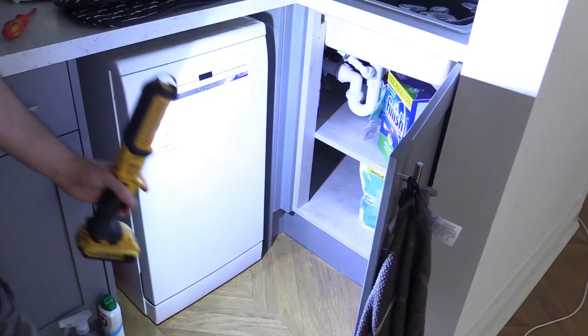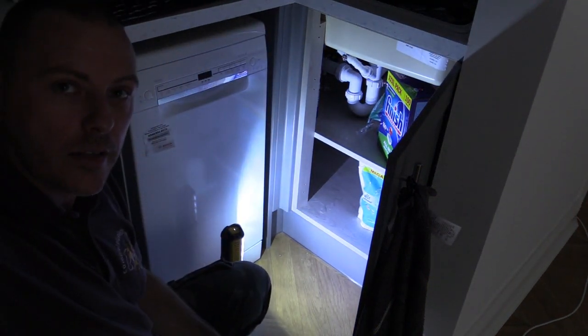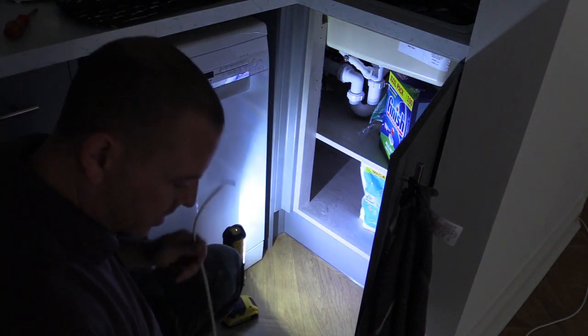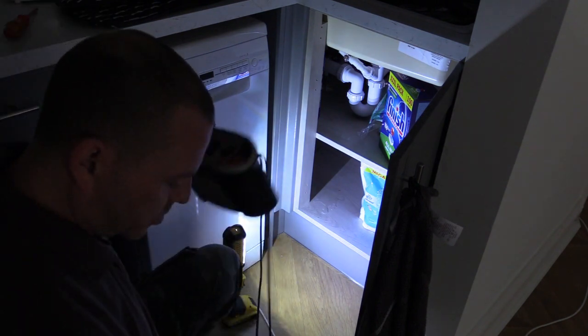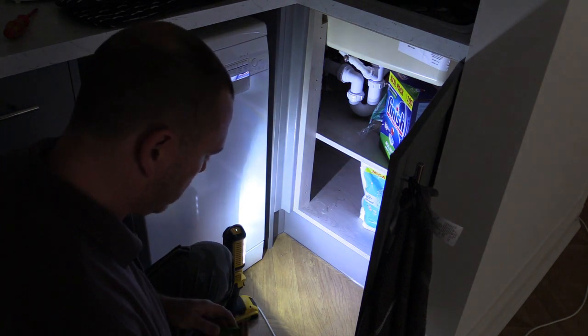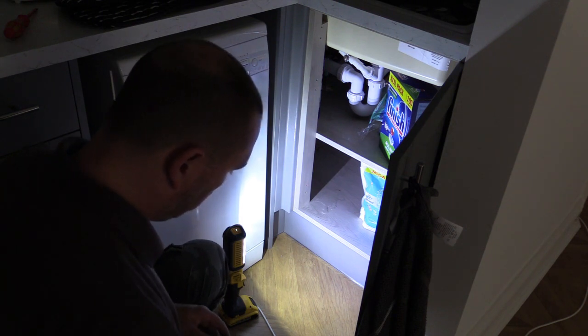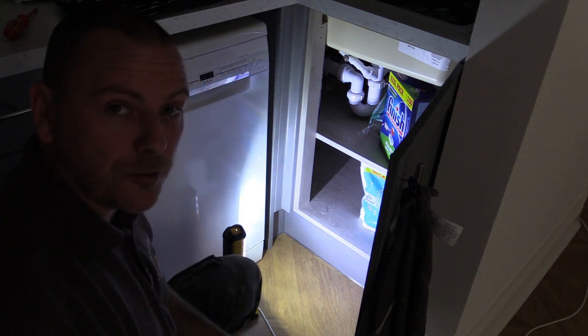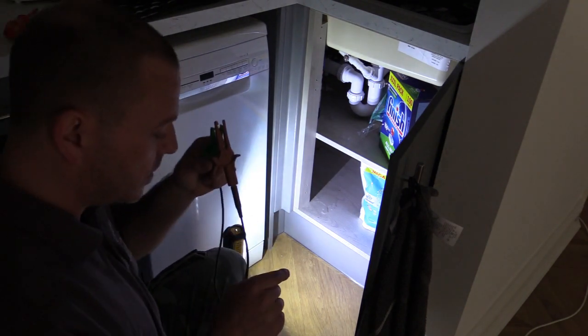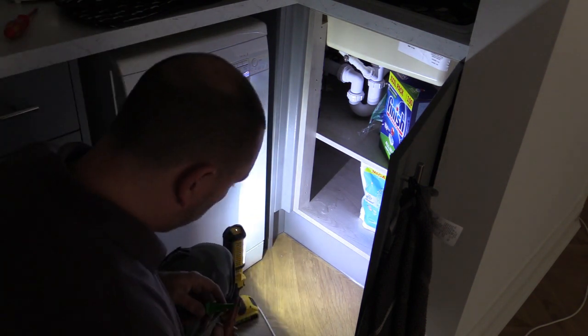Right, so I've joined it at the board. So I've taken the bonding conductor right out and linked it with my R2 lead, which is my bit of flex. Now this test kit also nulls the leads when you join them together, which is just Star Trek stuff for me. I never had that with my first test kit. I always had to deduct the lead resistance by joining them together, press test, write it down, do my test, then deduct that amount. But brilliant now, isn't it?